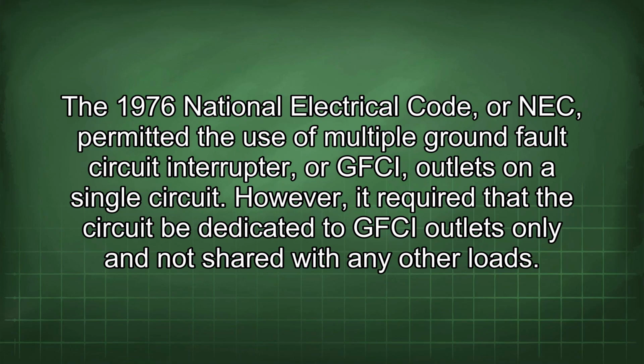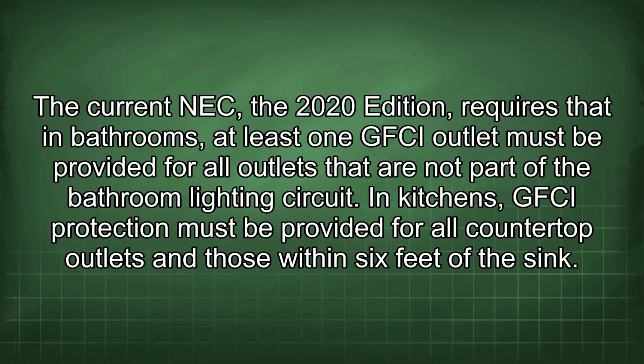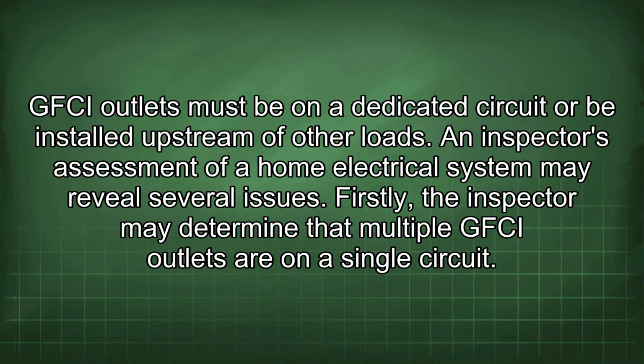The 1976 National Electrical Code, or NEC, permitted the use of multiple ground fault circuit interrupter, or GFCI, outlets on a single circuit. However, it required that the circuit be dedicated to GFCI outlets only and not shared with any other loads. The current NEC, the 2020 edition, requires that in bathrooms, at least one GFCI outlet must be provided for all outlets that are not part of the bathroom lighting circuit. In kitchens, GFCI protection must be provided for all countertop outlets and those within 6 feet of the sink. GFCI outlets must be on a dedicated circuit or be installed upstream of other loads.